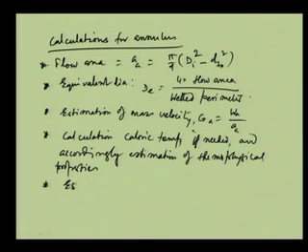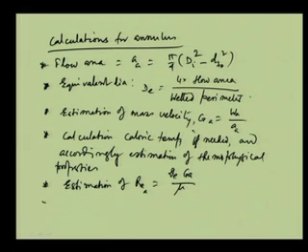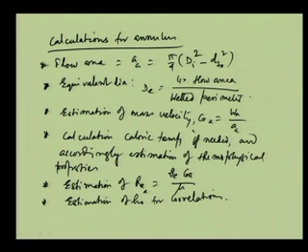And once we know that, then we have to go for estimation of Reynolds number. Okay, for annulus region, it is dE into GA by mu, and then estimation of HO from correlation, and then after we do that, we have the overall coefficient computation.